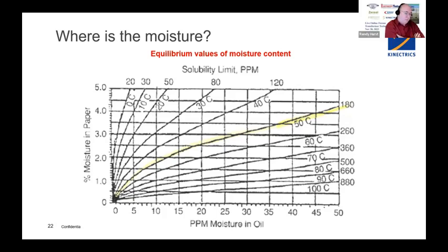Okay, what is the long-term benefit difference between periodic testing and live online testing, live monitoring? So I'm going to assume that we're talking about online monitoring of moisture content as opposed to taking periodic manual tests. My first part of the answer is I would always do both. I would never just rely on a monitor. And if you've got a monitor, again, as I said, take a holistic approach. Use all your data sources to make decisions relative to your asset. I don't think it should be one or the other.